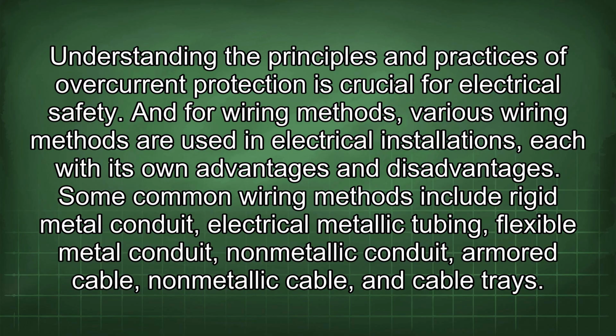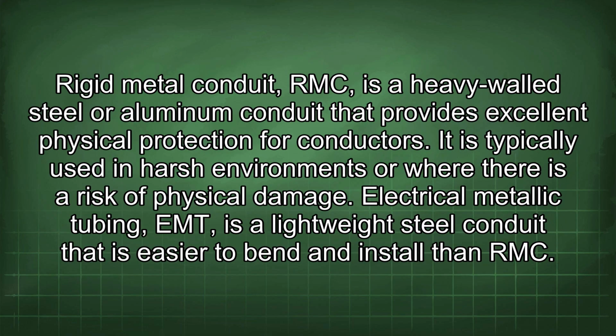And for wiring methods, various wiring methods are used in electrical installations, each with its own advantages and disadvantages. Some common wiring methods include rigid metal conduit, electrical metallic tubing, flexible metal conduit, non-metallic conduit, armored cable, non-metallic cable, and cable trays. Rigid metal conduit, RMC, is a heavy-walled steel or aluminum conduit that provides excellent physical protection for conductors. It is typically used in harsh environments or where there is a risk of physical damage.